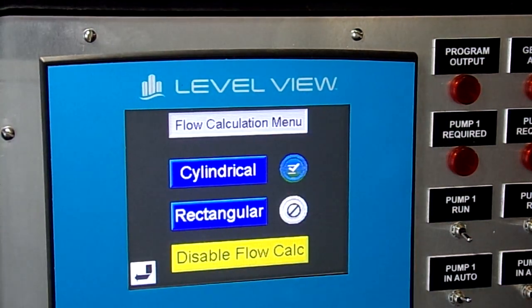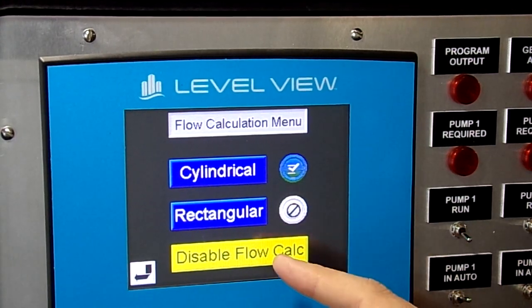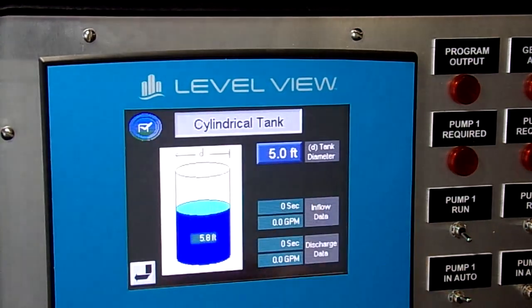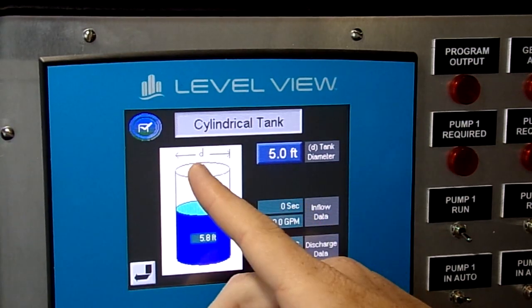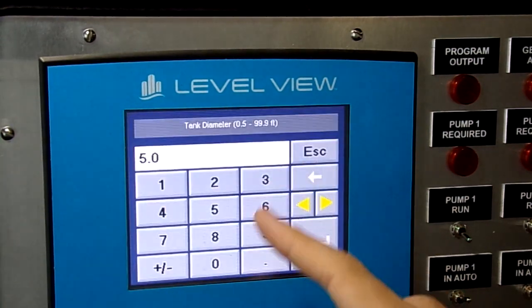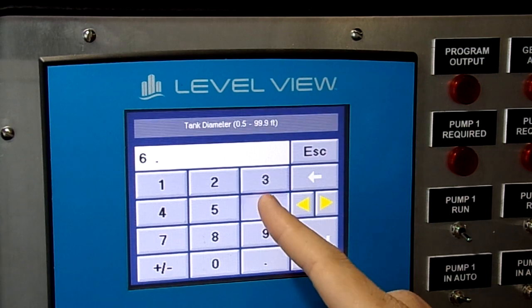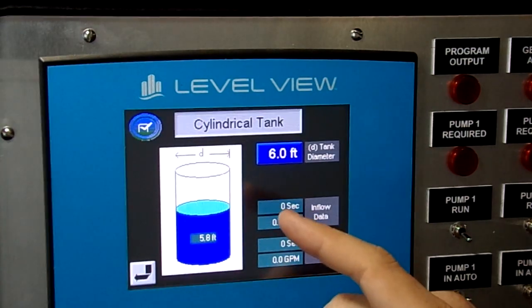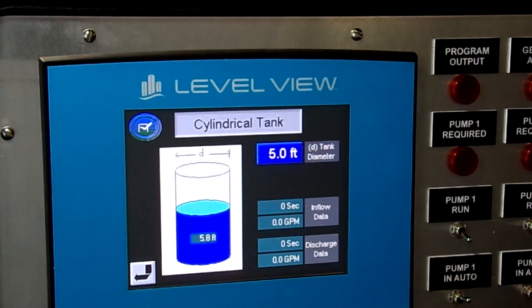This station also does volumetric flow calculations. So it'll calculate for cylindrical or rectangular tanks. So if you have a cylindrical tank, you'll need to set the diameter range right here to give you how many feet across your well is. So we can change that to 6 and back to 5.